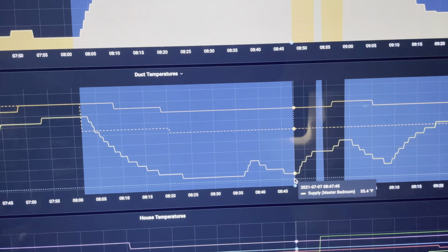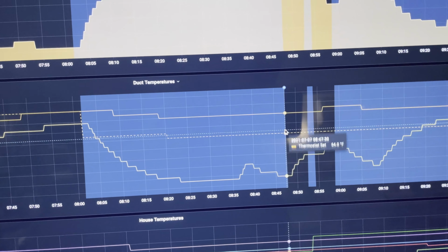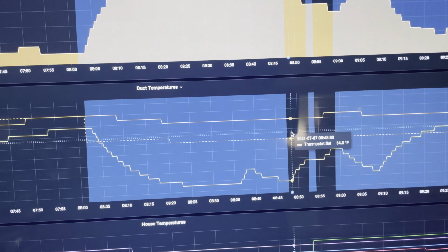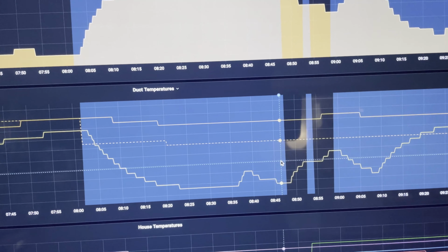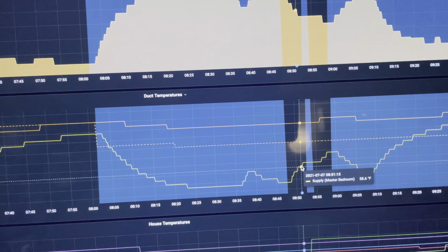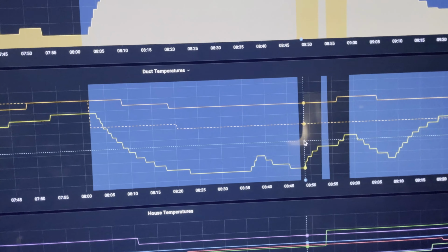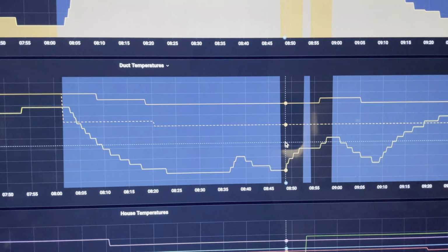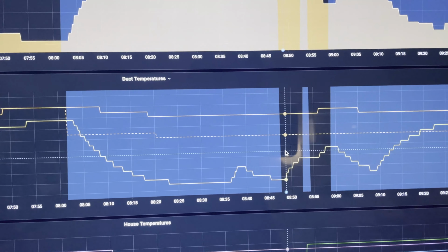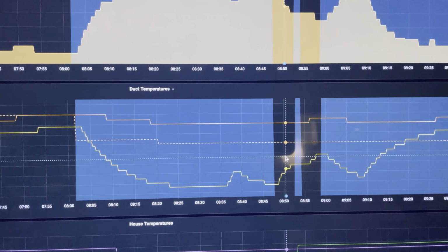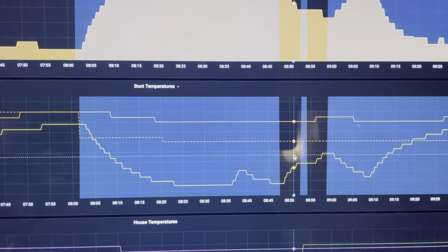Then what happened here? This is a very interesting spot. The set point is still 64. The house temperature is 68. It should be cooling, but all of a sudden the blue background goes away. It's not cooling anymore, and the temperature starts to rise. Well, this, which you'll see in the video that's posted, we had a mystery where all of a sudden, as he was putting the caps back on the service ports or whatever, the system just shut off and it went into a delay.